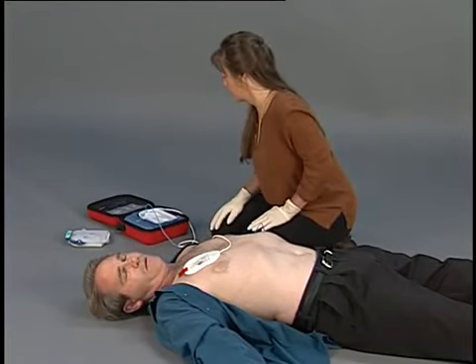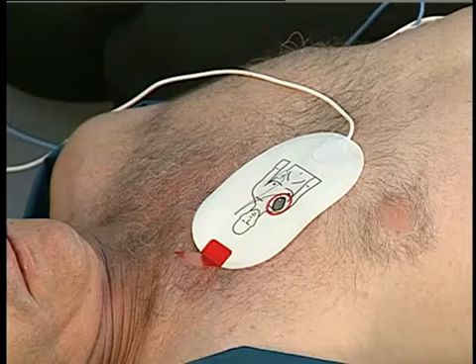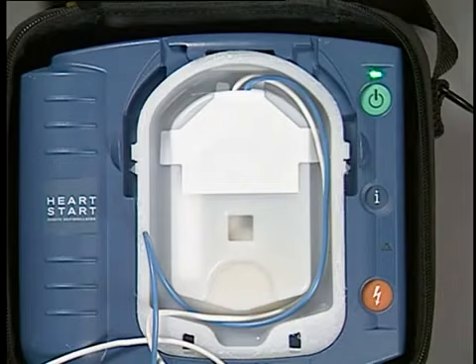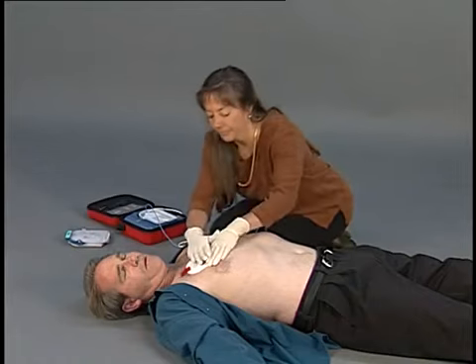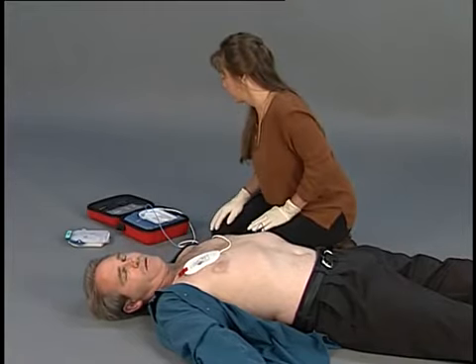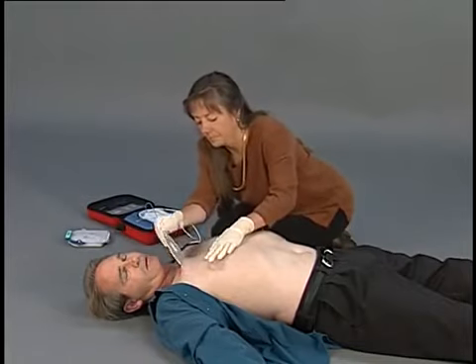If the HeartStart on-site defibrillator detects a problem while you are using it, it will provide a voice instruction to guide you in correcting the problem. Stay calm and follow the defibrillator's instructions. For example, if the HeartStart on-site tells you that the pads are not making good contact, make sure that the yellow plastic liner is completely removed from both pads. Place the pad exactly as shown in the picture. Pads must not be touching clothing or each other. You should press the pads firmly onto the patient's bare skin. Check that there is no obvious damage to the pads or the cable.